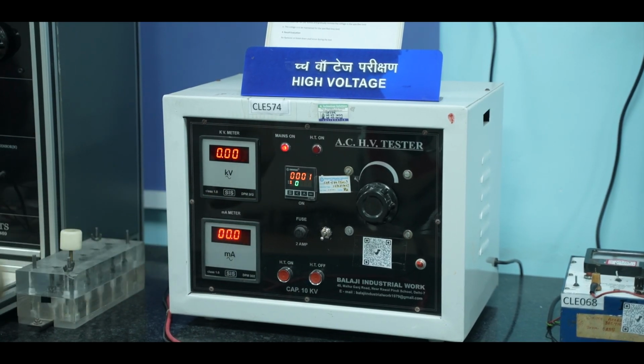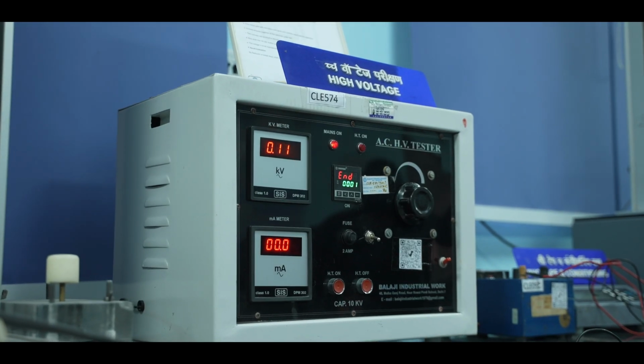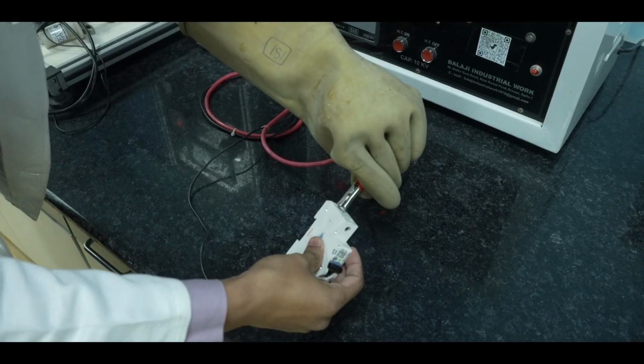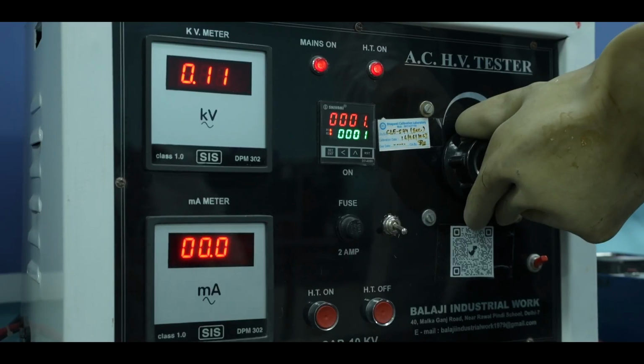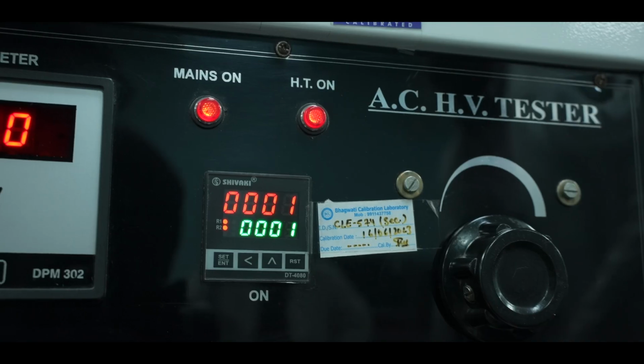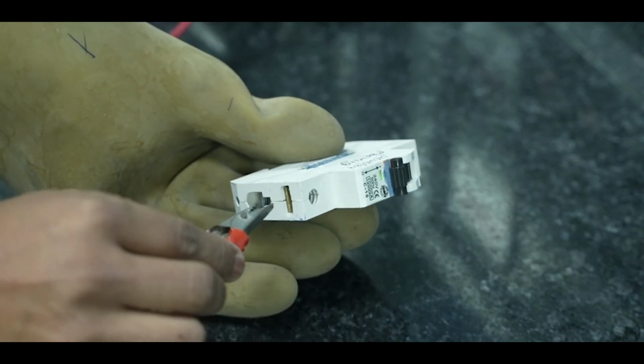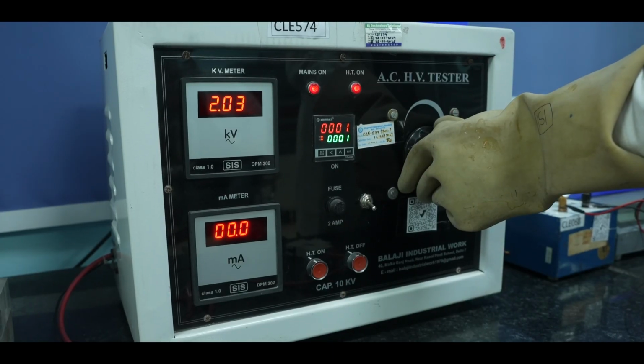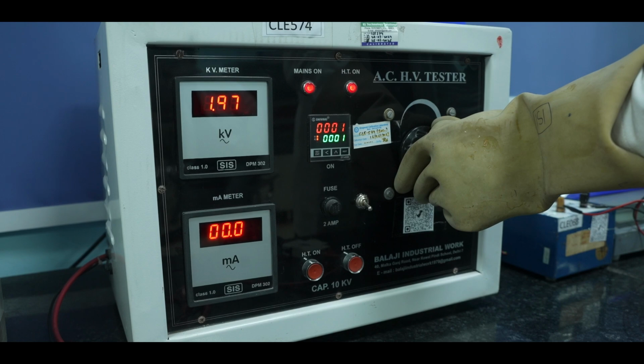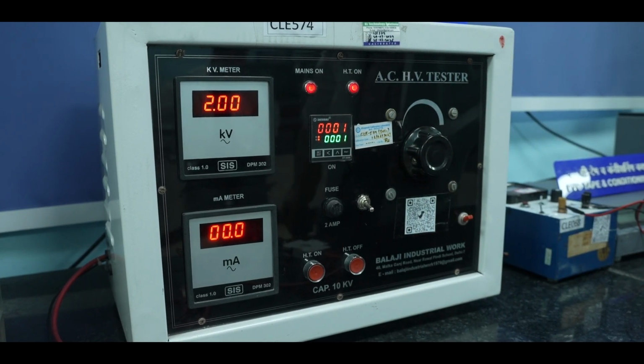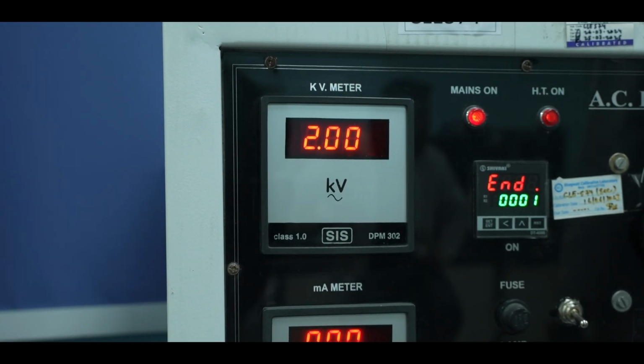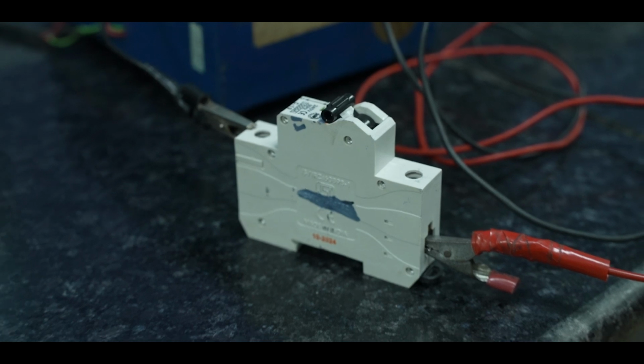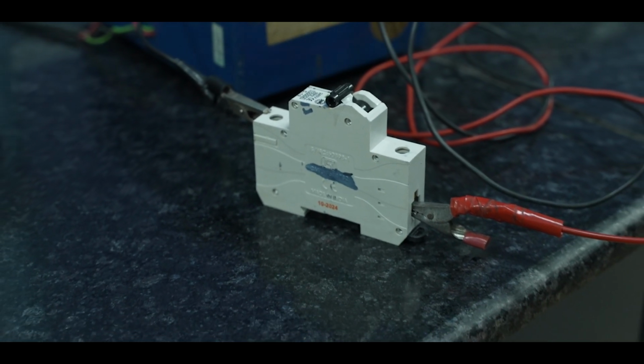Next, we verify dielectric strength. In this test, we apply a high voltage to check the strength of the insulation. The voltage is increased gradually and held for 1 minute between specific parts of the circuit. If the circuit is rated between 110 to 250 volts, we apply 2 kilovolts for testing. No sparks or damage should happen during the test.